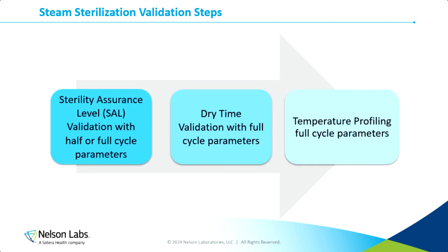Just as a quick overview, steam sterilization validations are performed by first performing the sterility assurance level or SAL validation using either the half or full cycle parameters of your sterilization procedure. That will be done three times, followed by a dry time validation with the full cycle parameters. Again, that is done three times in total, or three runs. And then finally, there is temperature profiling using full cycle parameters, where a temperature profile is made of the chamber and of the devices using the full sterilization cycle parameters.